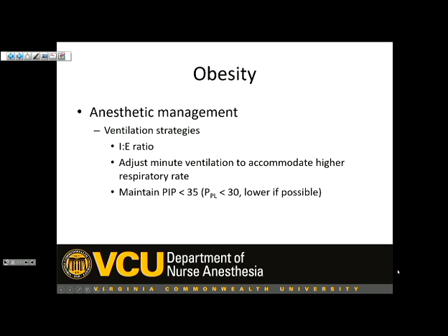The distance between breaths is uniform, versus in the patient who's triggering their own vent, that may not be a regular rate. So because this is what's on the dial, and we can do that because it makes sense for our particular ventilators and most of the patients that we will ventilate, we have IE ratio on the front of our vent. So that's what we talk about, adjusting the IE ratio, versus respiratory therapists who, again, are most often working with assisted modes, patient-triggered modes.